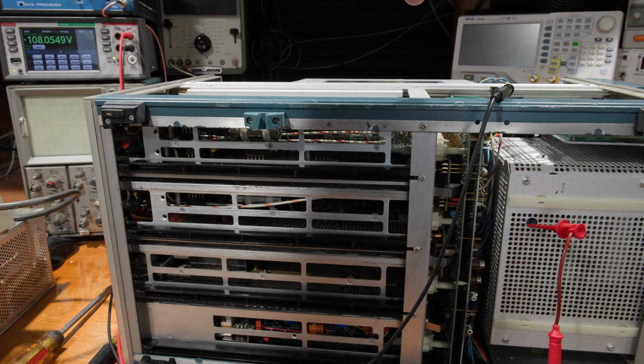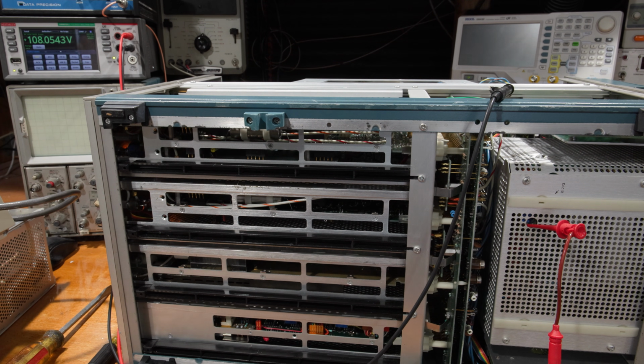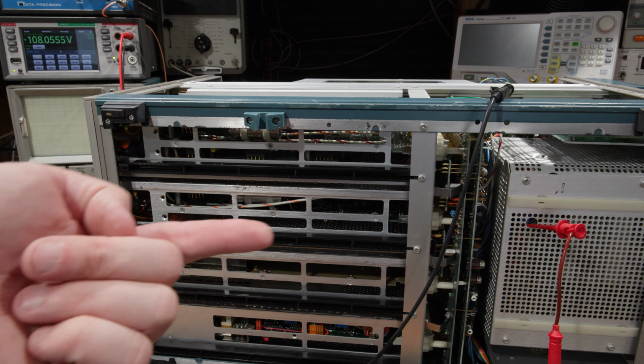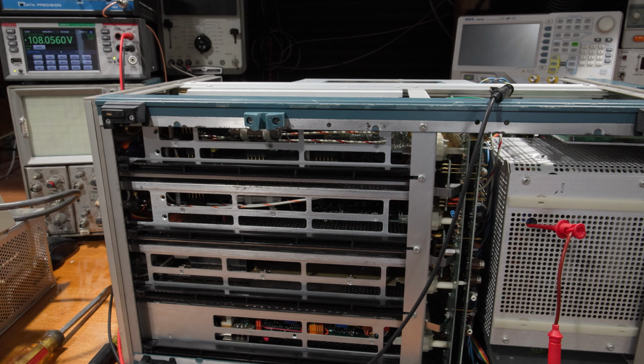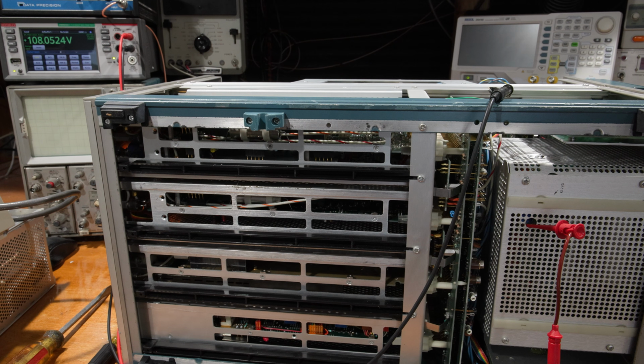Unregulated voltage has gotten through at the bottom of the power supply. Ground is just hooked to the chassis, and we're looking for 108, or 107.5 to 108.5. We're at 108.0, so right in the middle, and our pre-reg is good. Next stop, I've got to put the bottom cover back on, and then we have to pull the power supply out to expose the pins to take some measurements on the DC rails.